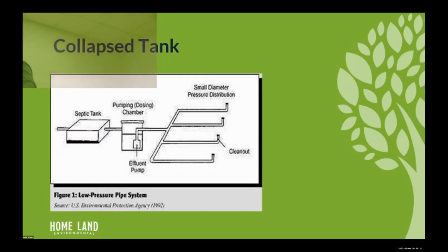We don't do it in an inspection, but if we did operations and maintenance for this homeowner, we would run that pump, and that pump should be pumping, I believe, 12 inches above the turnup. There's a stack where you can check the pump. These systems are about $15,000 because of the pump chamber and the pump. It really adds on. And with any type of alternative system, you have to put in a BAT tank in front of it, BRF, Bay Restoration Fund tank. That's another $15,000, so 15 plus 15, $30,000. Hopefully the BRF covers that tank portion of it, but they will not cover the absorption side of it. They will only cover the tank side of it. And if you're a builder, they're not going to cover it.